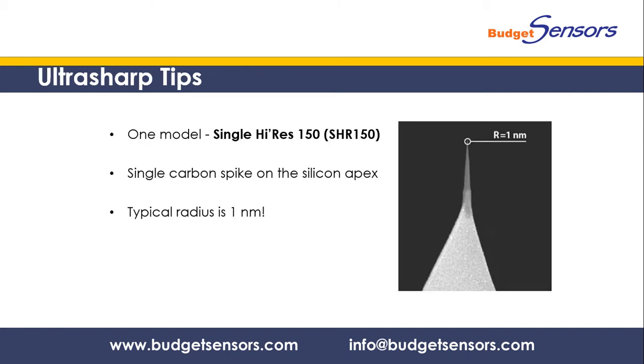For very high resolution measurements we have a special probe called the single high-res 150. This probe actually has the same basic tip structure as all other silicon tips, with one small but important exception. On the 10 nanometer silicon apex we have an ultra sharp carbon spike which makes the tip almost 10 times sharper. The tip radius in this case is around 1 nanometer only. This probe is actually a modified TAP 150 probe and it is meant for soft tapping mode imaging of very fine features in the low nanometer and the sub-nanometer region.